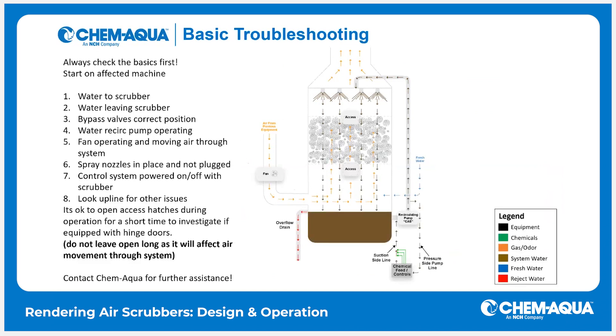For basic troubleshooting, the most common issues in a wet air scrubber: first and foremost, make sure there's water to the scrubber — if somebody's accidentally turned off a valve, we won't get water into the machine. Secondly, water needs to be leaving the machine — check for plugged drains or closed overflows. Also check all bypass valves. If you have a chemical control or makeup water feed control system, those will have an emergency bypass. If a bypass valve is open, the system can't see what's going on and may operate improperly.